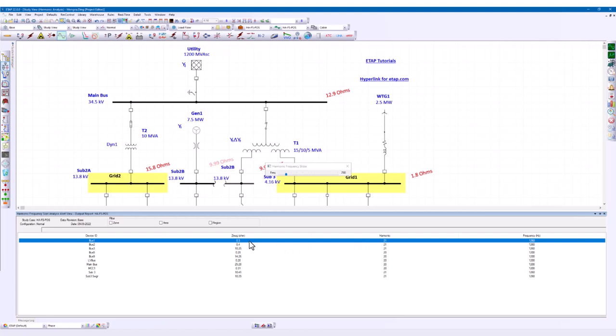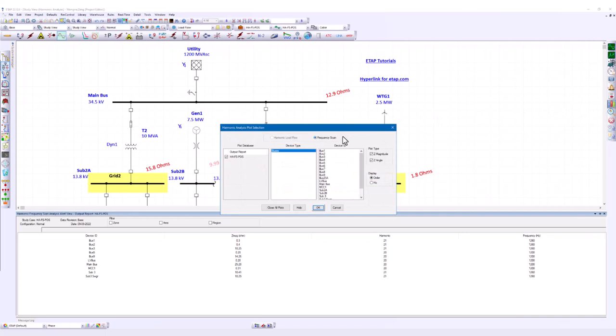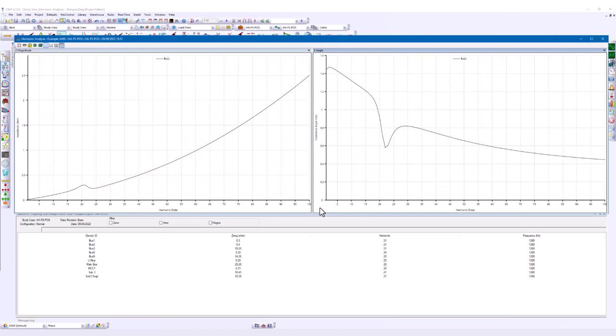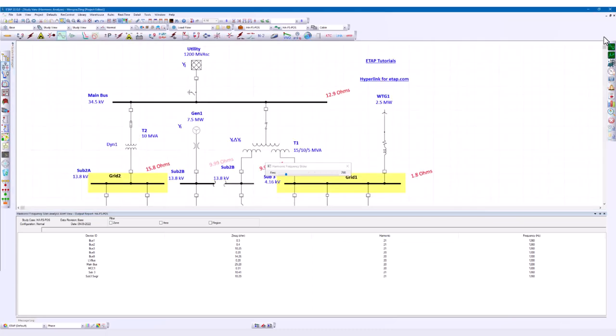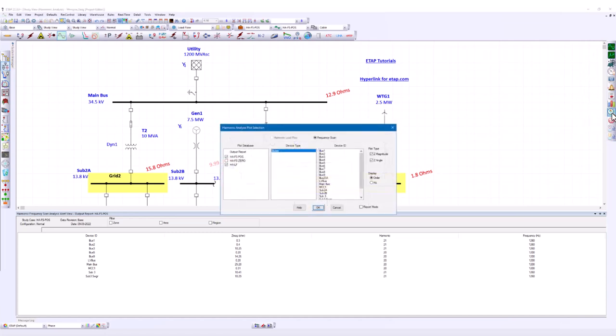Now, if we want to take a look at the plot for bus 1, let's go to the harmonic analysis plots. Let's select a frequency scan, bus 1, and we'll plot Z magnitude, Z angle, and order for bus 1. Based on the plot, you will see there's a peak for order 21, which is the same information as was shown in the alert view. Similar to harmonic load flow calculation, we provide the plot analyzer option as well.